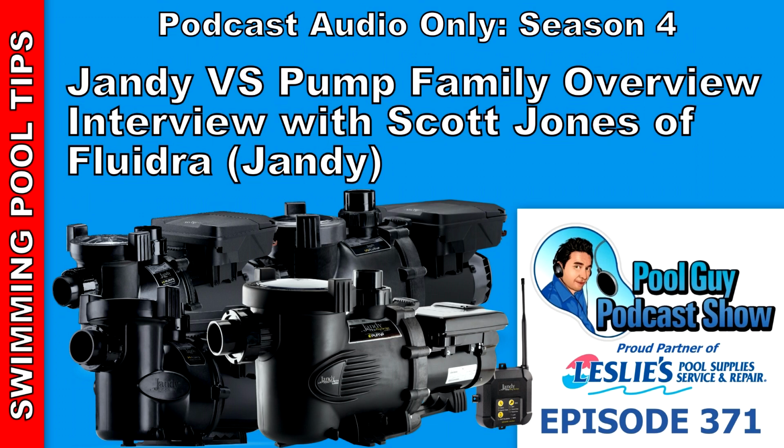We simply recommend that, if you're running your heater through it, make sure that when you go from, say, 1750 RPM, it just doesn't go from an on to an off state. You would go from 1750 RPM down to, say, 1500 RPM, so that you're still having water run through that heater and you're allowing it to cool down to protect that heater. That heater is an expensive piece of equipment, and we wouldn't want to see things damaged by using it. So there's ways to do it. You just need to be smart about it.